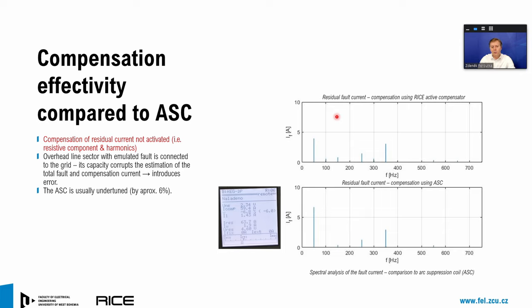We also evaluated the effectivity of our device in comparison to the arc suppression coil. Nevertheless, we stressed our device under very strict conditions. We turned off the compensation of the residual current. It means that we turned off the compensation of the active component of the fault current as well as higher harmonics, because the arc suppression coil is unable to do it.